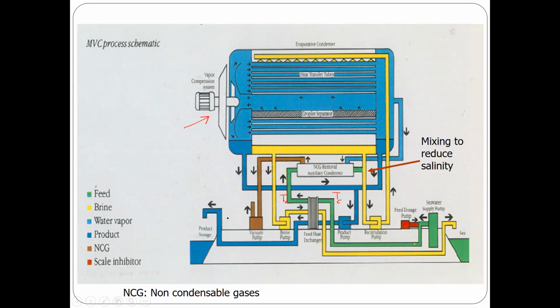There's something interesting here in this figure, which is I just made this addition today, just showing here that the brine, which is leaving the unit, is recirculated back. The brine is leaving at saturation temperature, which is right here. And then as it leaves down there, here it is mixing with the seawater. So you are mixing the seawater with the rejected brine.